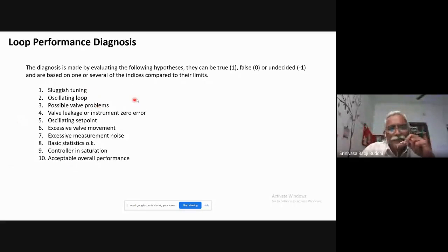Okay. When we evaluate this hypothesis, you can come up with results that it can be either true. That means if, for sluggish tuning, based on, say, autocorrelation coefficients, I find that the loop has a sluggish response, if the index value is more than the limit, then we say that it is true that it has sluggish tuning. Or if it is not there, then we say that it is false. It is not having that particular issue. Sometimes, because we are dealing with real life data, we may not be able to conclude anything correctly, either false or true. So we leave those cases undecided also. Okay. So like this, when we evaluate, we come up with results for each of these assumptions or hypotheses.